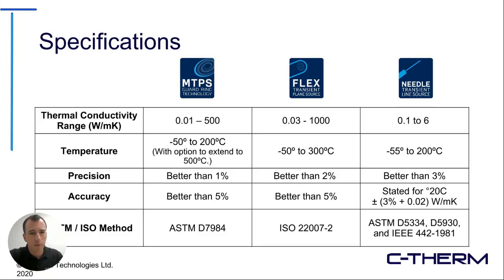This slide just gives you a quick comparison of some of the specs for those different methods. MTPS and Flex TPS, they offer very similar accuracies and precisions overall. MTPS is the easiest to do. If you had different sites around the world running the same test, we would recommend MTPS first because it's the simplest to run. So quite often the variability in performing a test is introduced by the operator, and the simpler you can make it to run the test, the better your statement of reproducibility is between different labs and facilities. So for that reason, MTPS has some significant advantage.